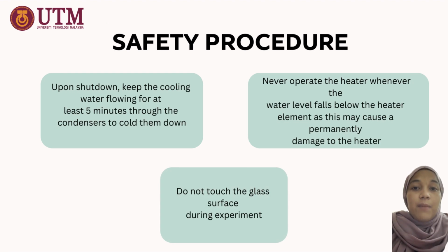There are 3 safety procedures that our group has listed out during the experiment. First, upon shutdown, keep the cooling water flowing for at least 5 minutes through the condensers to cool them down. Second, never operate the heater whenever the water level falls below the heater element, as this may cause permanent damage to the heater. And the last one, do not touch the glass surface during the experiment.